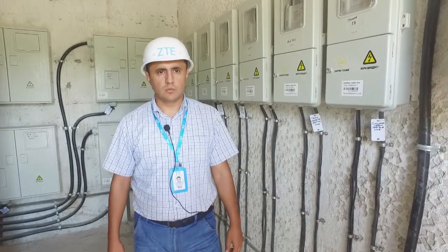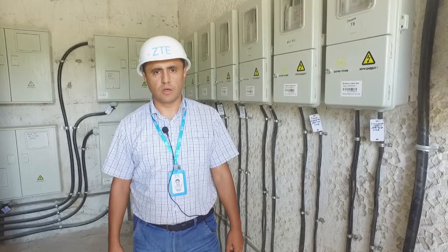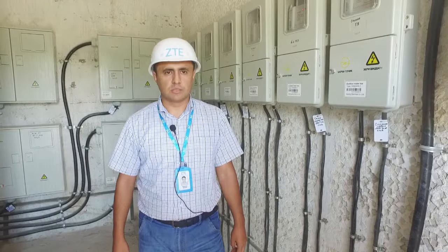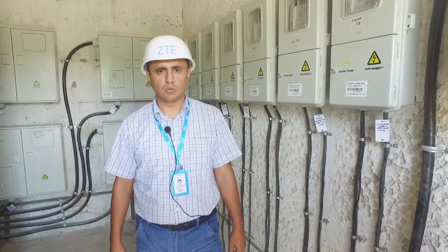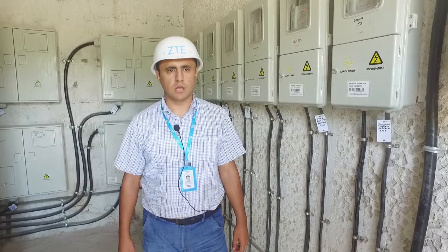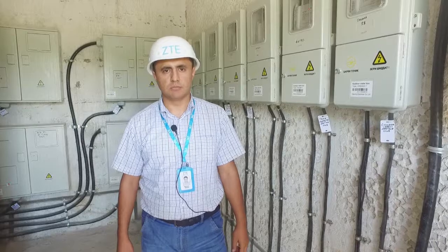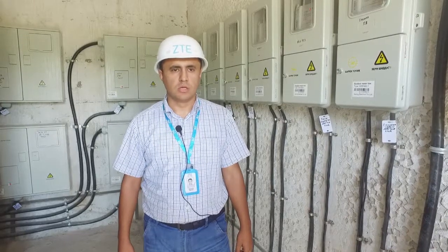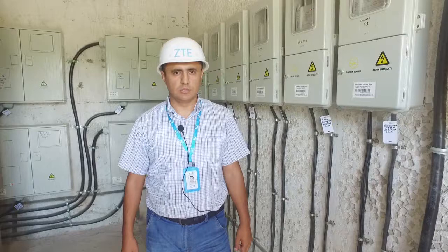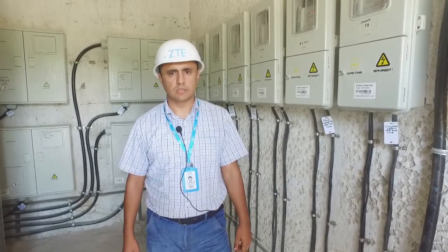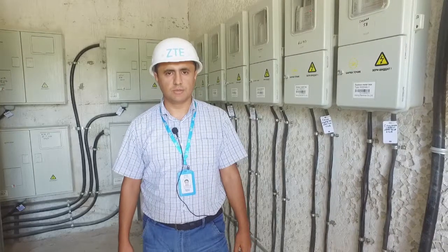A PLC collector is a device which is located inside any type of meter box. Its function is to collect meters' reading data through the M-bus wire between the PLC collector and the meter, receive and send signaling data such as meter power off and on, and send the collected data to the DC, the data concentrator, through PLC technology by using the existing power cable line from the meter to the transformer. The GPRS collector has the same function as the PLC collector.